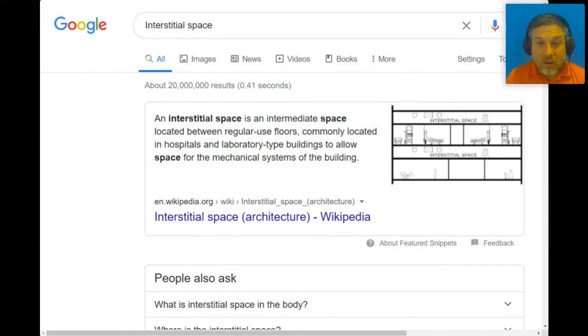If it's really large and there could be over 4 people, I don't think there's any other way to fit other than the service space mezzanine. So then they have to look at, I need to have 50 meters to an exit. If it's a certain size, I need to have egress to the area below at certain intervals. I've seen where they use ladders, because you can use ladders. So every so often, they're going to provide ladders to the space below. And then they have to provide an exit within 50 meters.